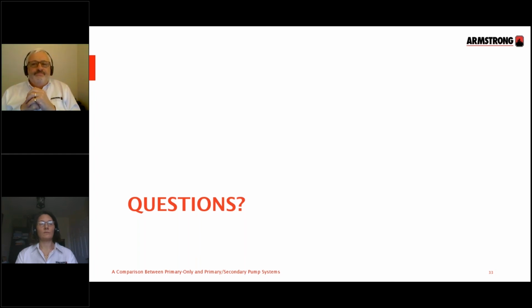Thank you, Peter. The last and final question, we are a little bit out of time here. I have been hearing a lot about parallel sensorless pump control. Based on this sensorless pump control technology, is it always best to run 2 pumps at a minimum? Short answer is no. It depends upon where the duty point sits at the moment in time versus the best efficiency number of the pump. If the duty is to the left of best efficiency of that pump, it doesn't make any sense to energize a second pump and then be even further to the left. So it's not a one-size-fits-all answer. It's not always the case that 2 pumps are always better than 1. It depends on where the duty point sits relative to the efficiency of that pump.